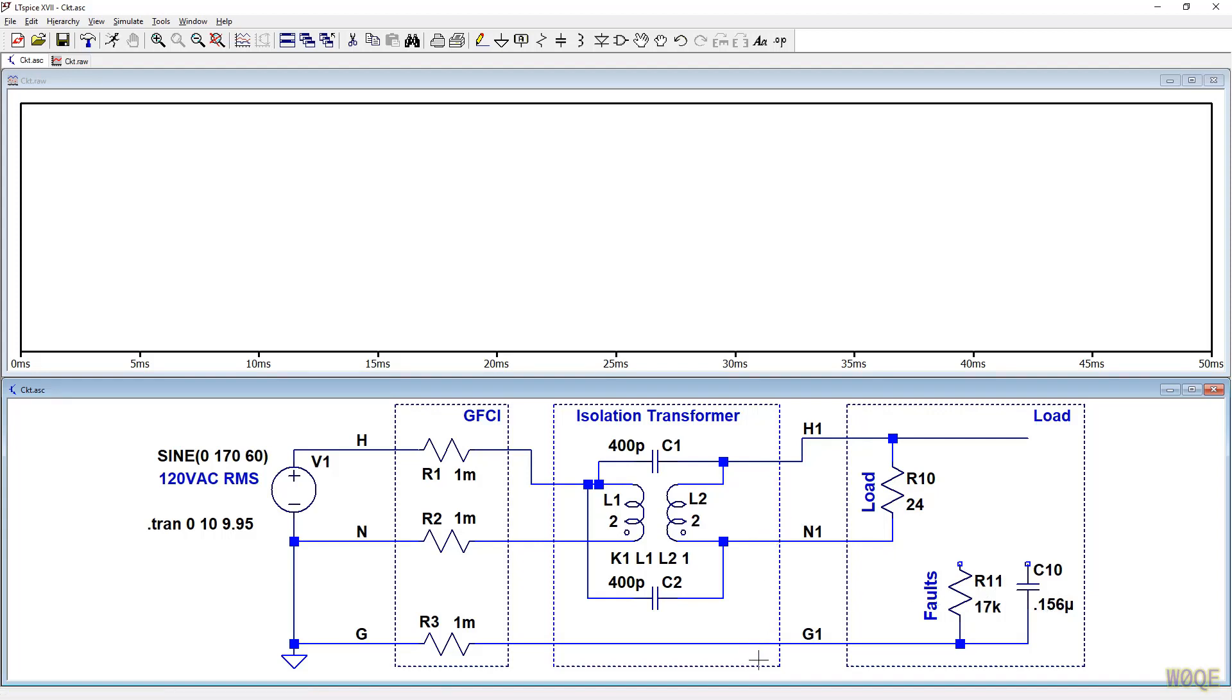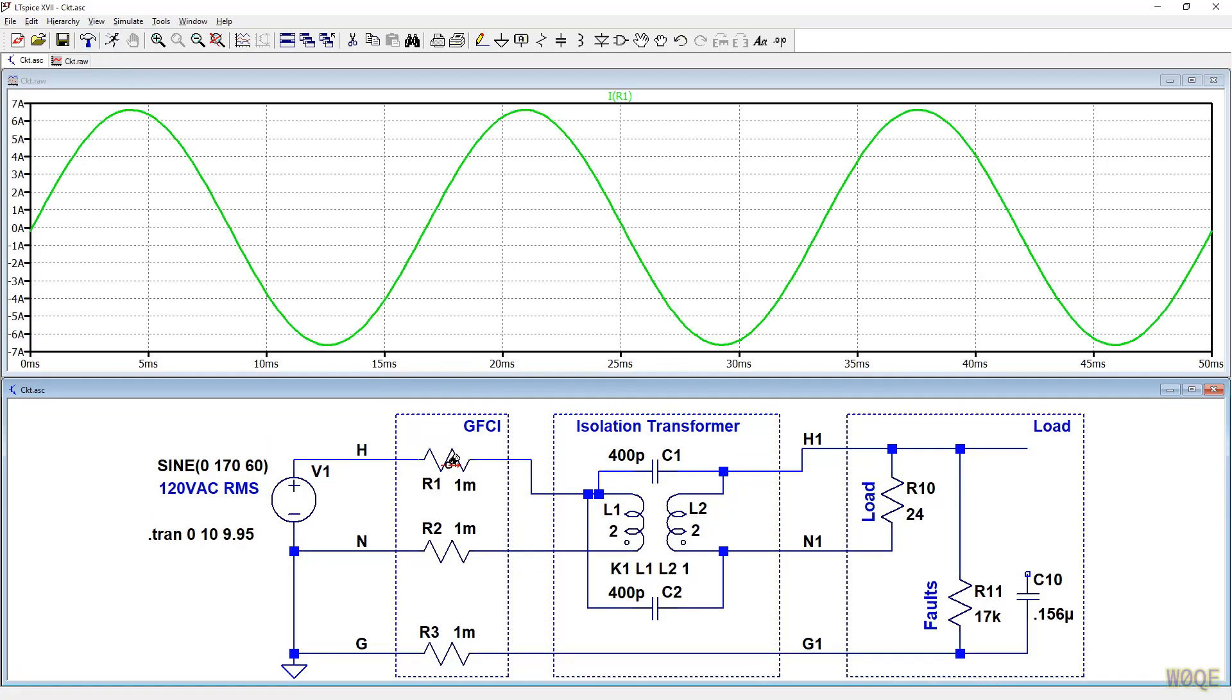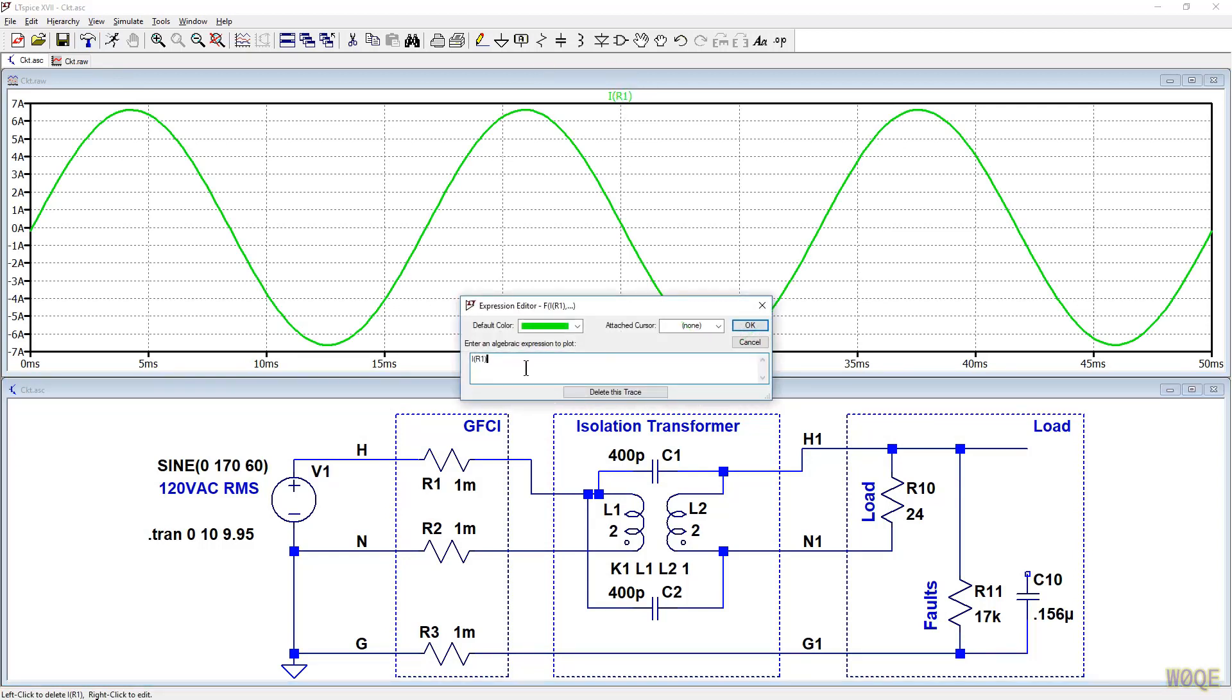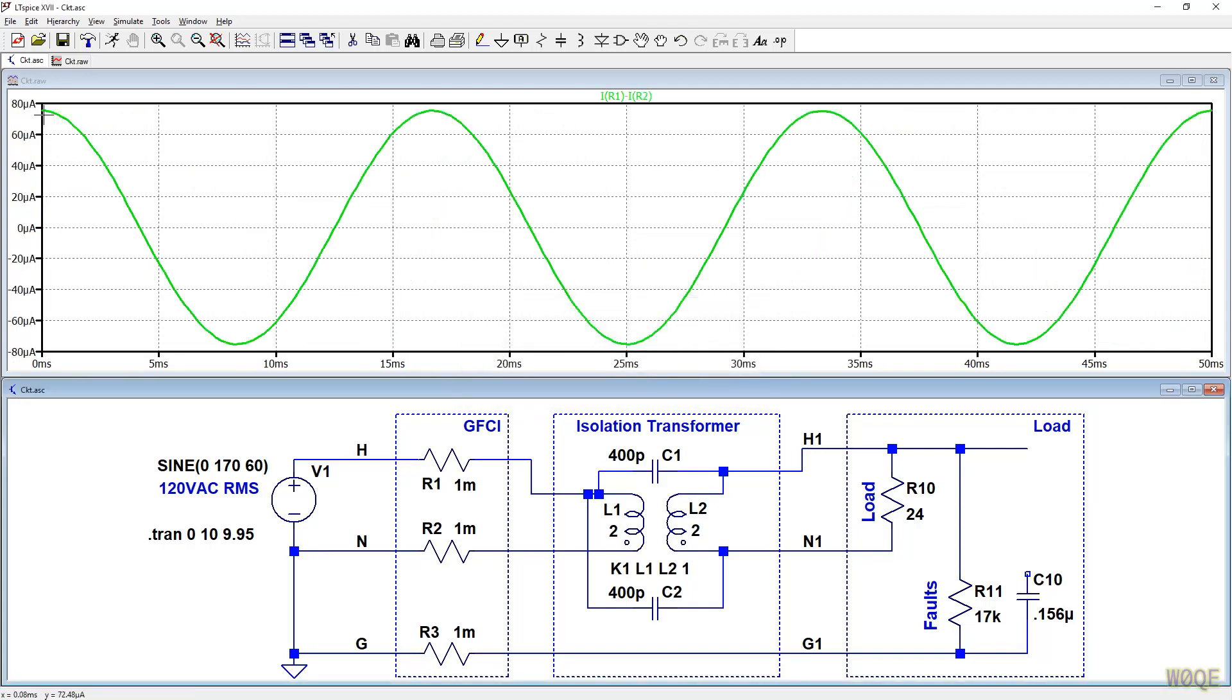And I've got a 24 ohm load like I had before it will draw five amps and I've got these two fault conditions. I do not have a connection from here to ground at the moment. Let's just leave this as an isolation transformer. If I had a fault here I wouldn't be able to see it. This point would just move right down to ground, very little current would flow here and what we would see here wouldn't be enough to trip the GFCI. Let's run this circuit and subtract the two currents and what I see is an 80 microamp peak current that flows here well below four or five milliamps that would trip the GFCI and that's with a current here flowing that would have been 10 milliamps peak.